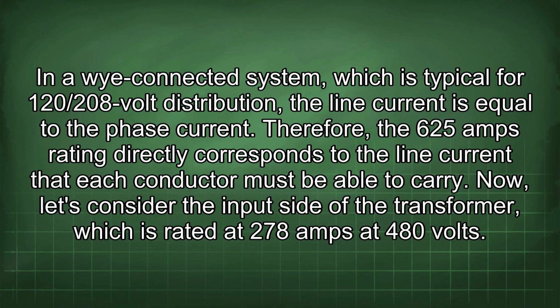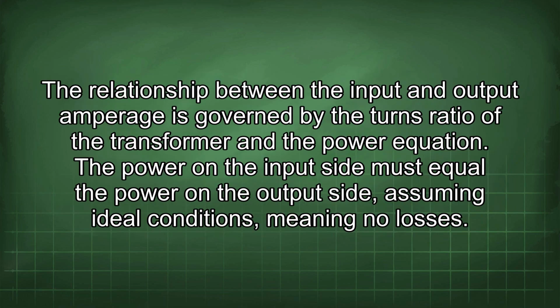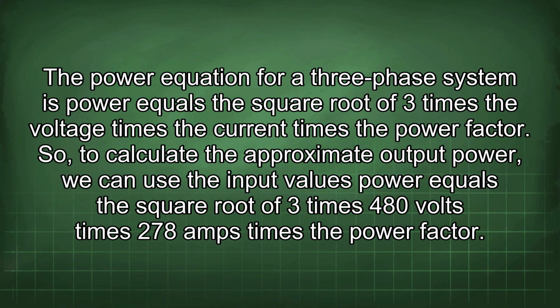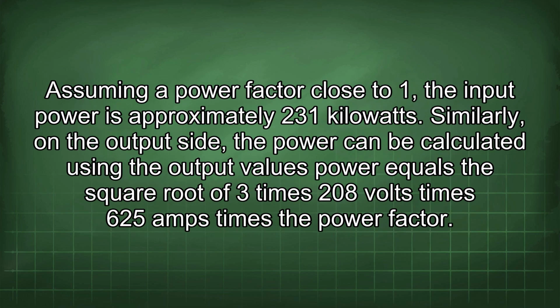Now, let's consider the input side of the transformer, which is rated at 278 amps at 480 volts. The relationship between the input and output amperage is governed by the turns ratio of the transformer and the power equation. The power on the input side must equal the power on the output side, assuming ideal conditions, meaning no losses. The power equation for a three-phase system is power equals the square root of 3 times the voltage times the current times the power factor. So, to calculate the approximate input power, we can use the input values: power equals the square root of 3 times 480 volts times 278 amps times the power factor. Assuming a power factor close to 1, the input power is approximately 231 kilowatts.